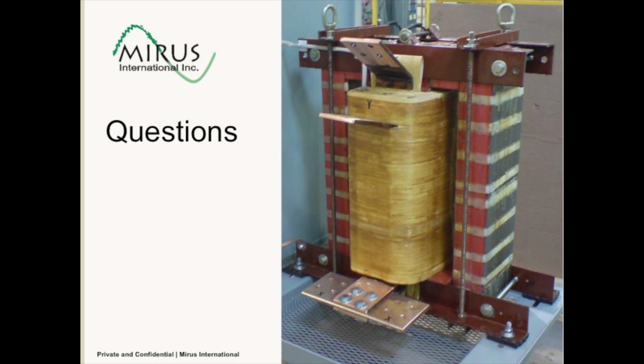Okay, our first question is, in the design phase, can you calculate or predict the level of circulating current you would expect on the system with two different pitch generators? Well, as you saw, there was one generator manufacturer that does a model to calculate what they would expect for the circulating currents. We can apply our impedance, zero sequence impedance, into that model, and we can predict that.